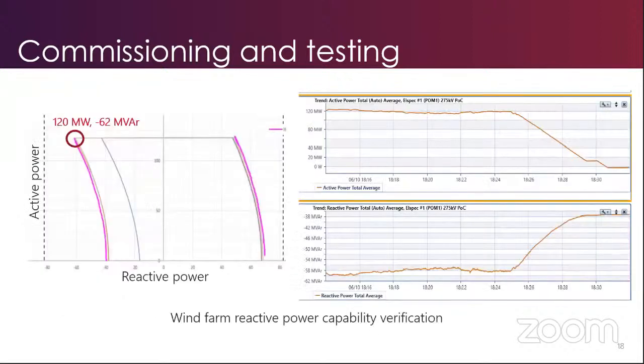Showing an example of commissioning testing. This particular plant has an agreed performance requirement of 120 megawatts. It has to generate and absorb 62 MVAr, and the plot shows it operating at 120. Through the verification test, they have proved that they can operate at about 62 MVAr absorbing.